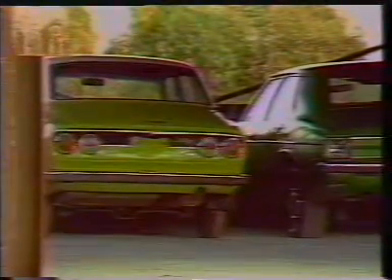5 recent model cars were parked in a typical open-deck car park, so that the spacing between cars was about 400 millimetres. The cars were chosen as being typical of modern cars, with representative quantities of combustible materials. The petrol tank of each car was filled to 1/2 capacity. The first test was conducted on the 21st of May and was witnessed by a large group of engineers and people representing building regulatory authorities.